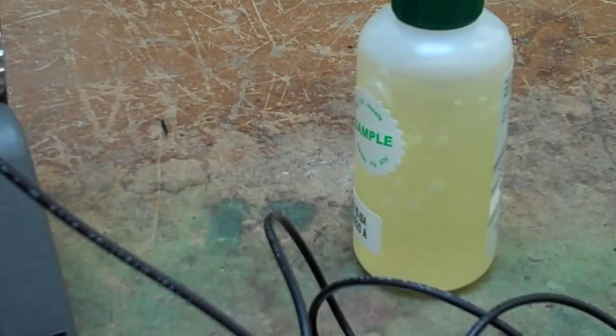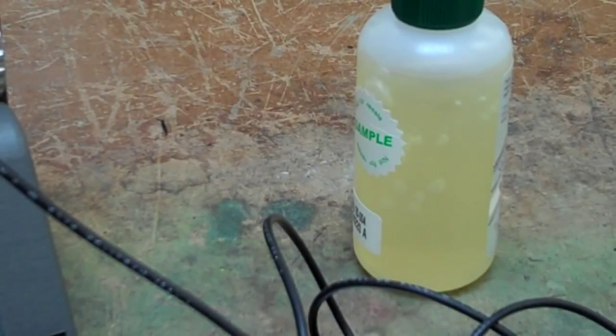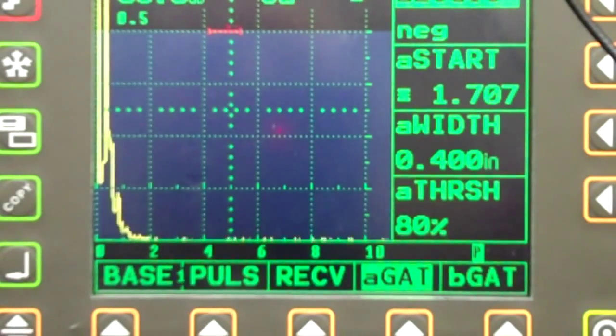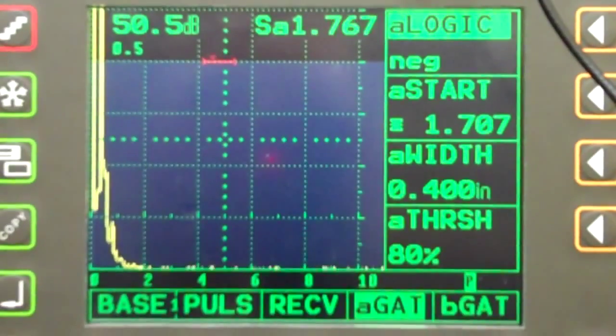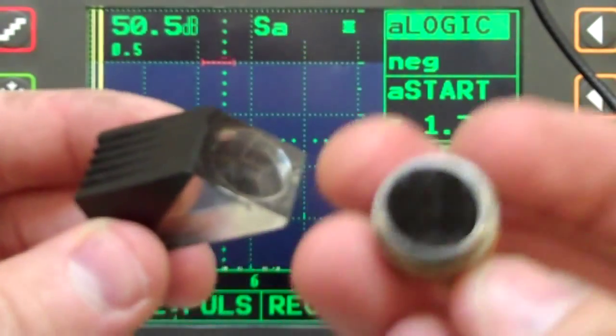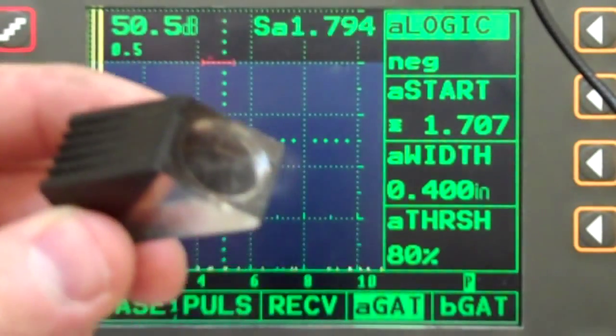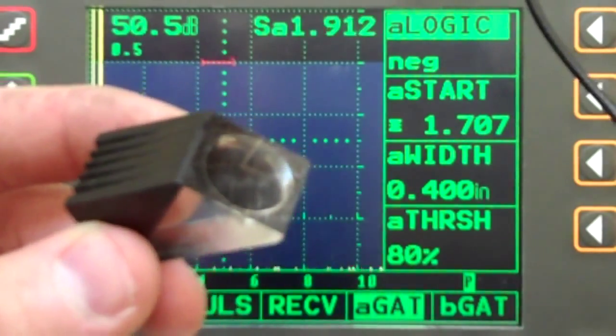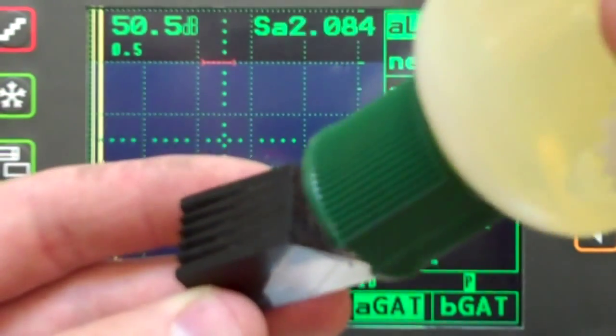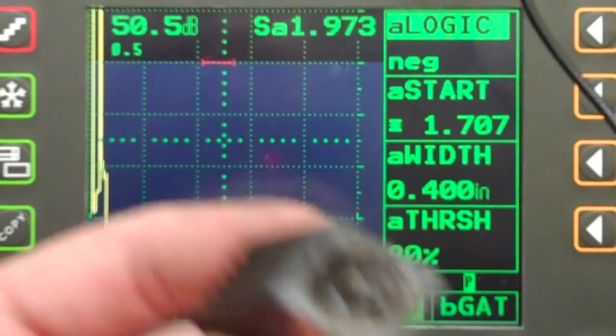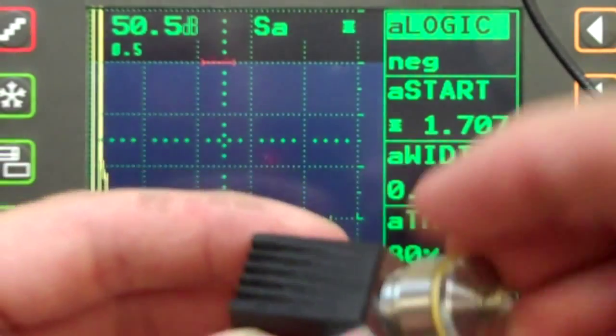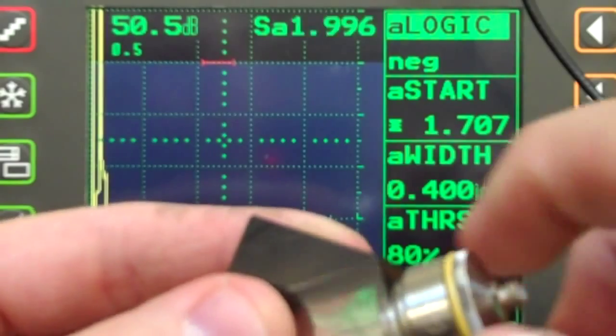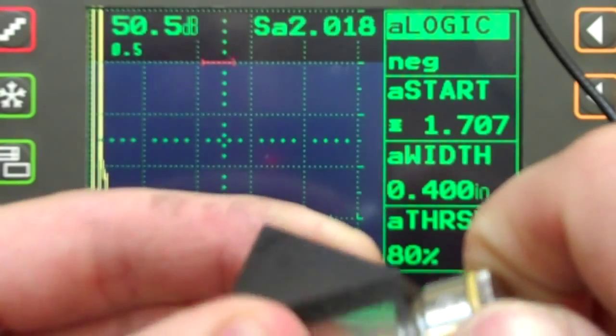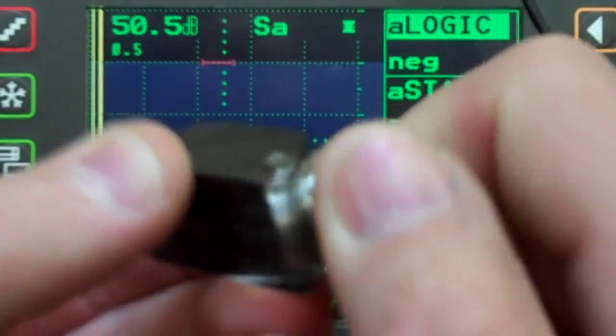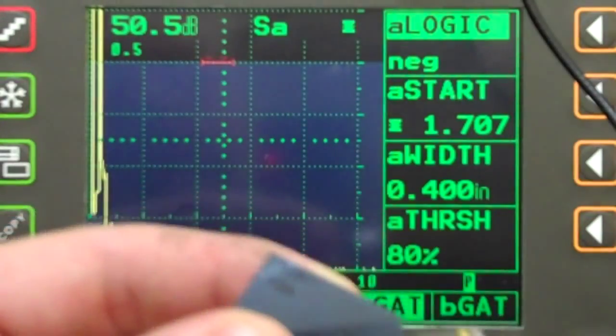I took the transducer out. I want to put a little couplant between the transducer and the wedge. Come back to our screen here. Here's the wedge. Here's our transducer. Like I said, I'm going to put a little couplant between the two. So I'm going to take my bottle of couplant, just a drop. Don't need a lot. Okay, so just put a little drop of couplant there. And that's just to couple the transducer to the wedge. And you see it squeeze out a little couplant right there. So get rid of that.